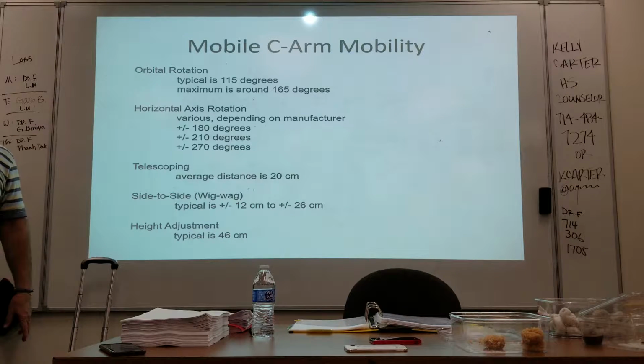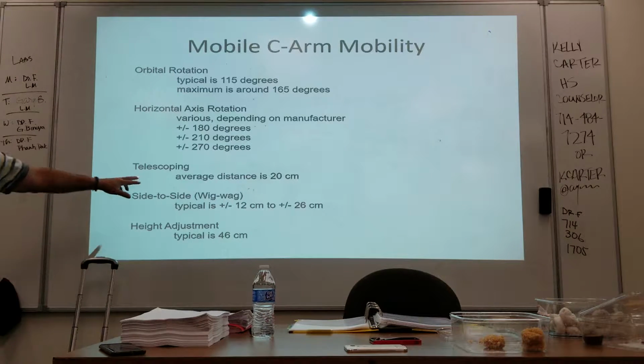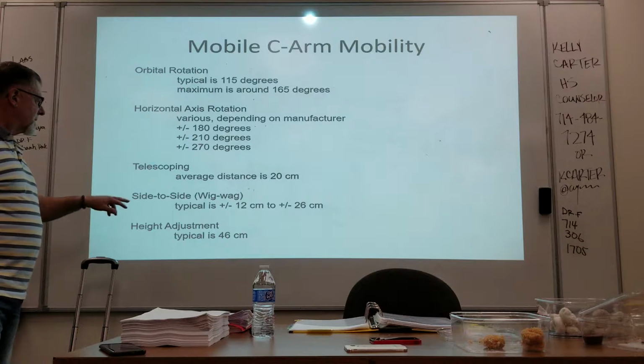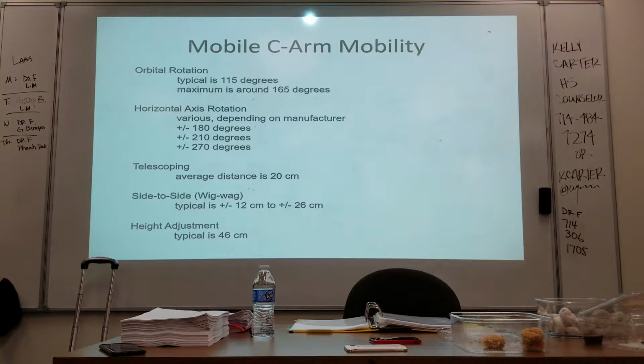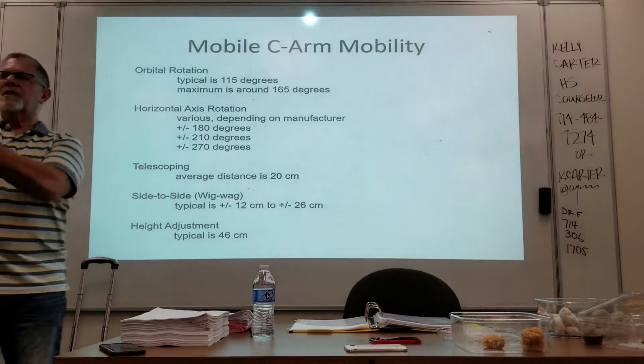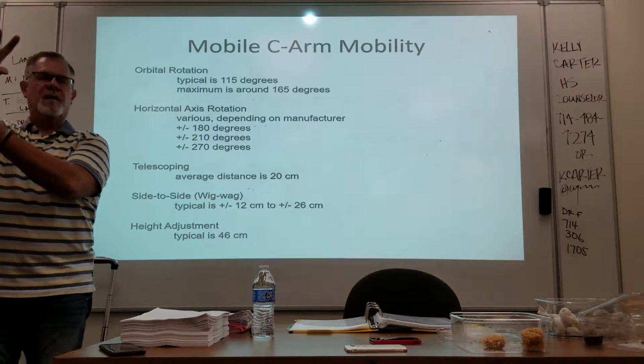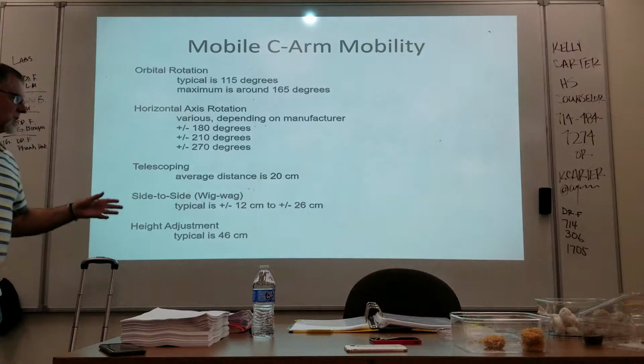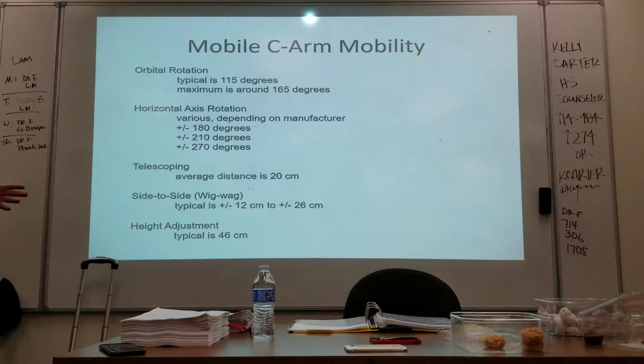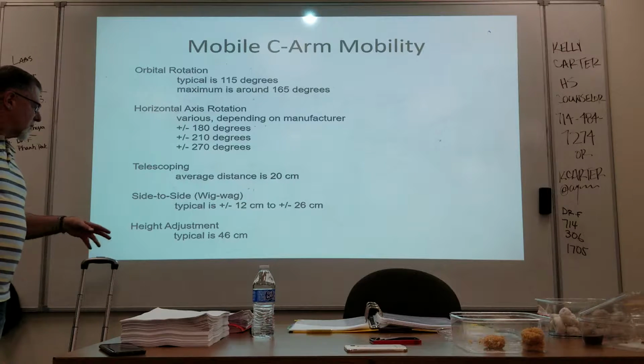Telescoping, this is where you move the C in and out. Average distance is typically around 20 centimeters. Some manufacturers a little more, some manufacturers a little less, but that's a good estimate. Side to side, what they call wig-wag, that's where the C goes this way. Typical is plus or minus 12 centimeters, plus or minus 26. So it's not a lot, but it allows you to do some. It means you get it close enough, then you can make fine adjustments depending on where the patient is.